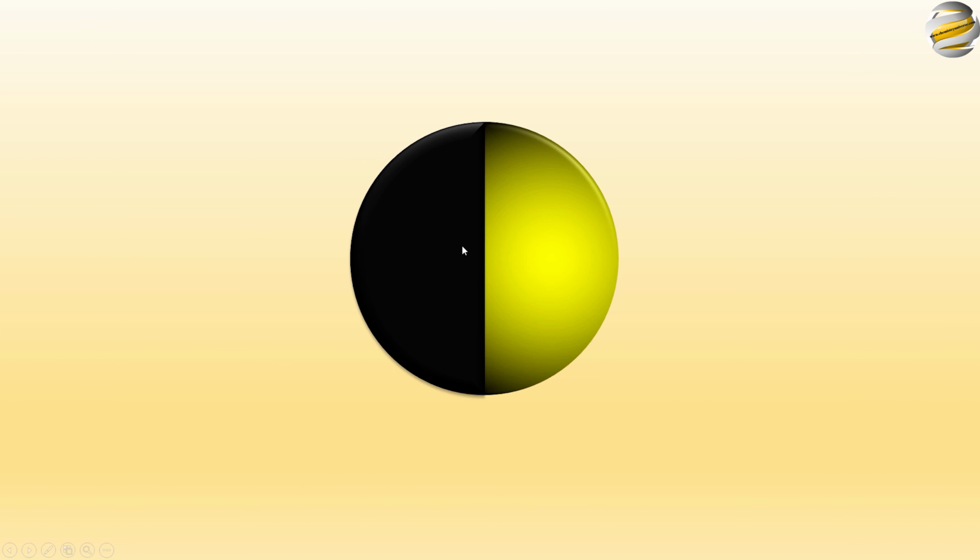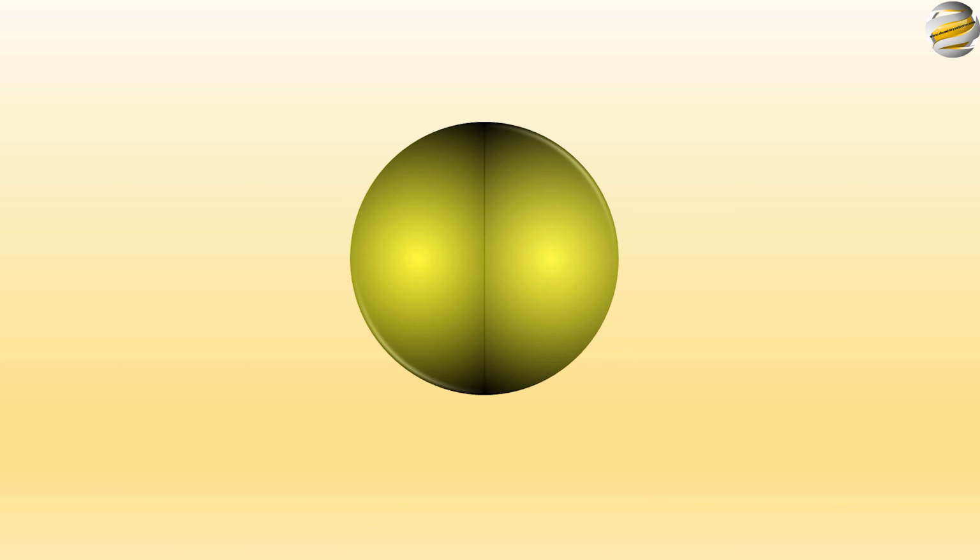If the analyzer is rotated by 90 degrees, then the quartz half becomes bright and the glass half will be dark. The analyzer is kept exactly midway between these points, where both halves will be equally bright, and this brightness will be lower than the maximum brightness of each half individually. It is easier to compare two bright semicircles than to try to achieve absolute complete darkness of a bright circle.